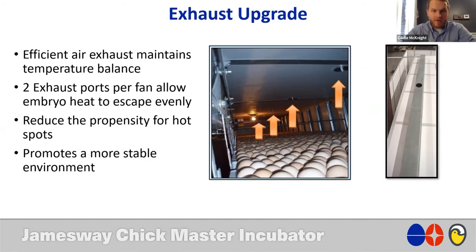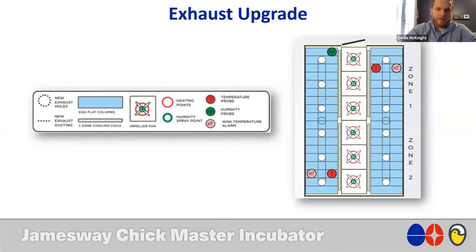The 2 exhaust ports per fan help reduce the propensity for hot spots inside your machine. You're going to keep hearing me talk about stable environments. All these upgrades help achieve a more sustainable, more stable environment inside your incubation cabinets, and that's invaluable. As you can see in this diagram, the exhaust upgrade takes you from a limited number of exhaust ports to 6 running down each side, 2 per fan zone. So as heat is generated, it evenly disperses out of the machine and gets pulled out as you want it to.